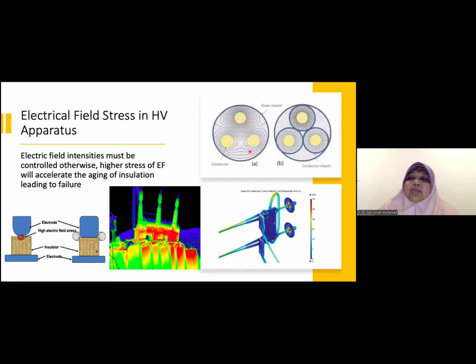So here is some software that we can use to study the E field. This is an example of a transformer. This is a cable, a three-phase cable. We study the E field distribution. Then when we add the shield, we can see that the E field distribution becomes more uniform. The stress in this area is more uniform compared to here. So now this improves the design of the cable.